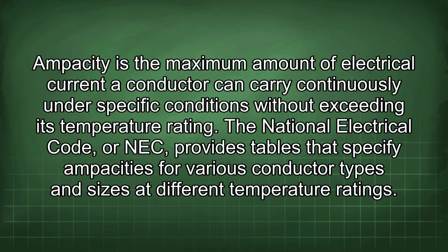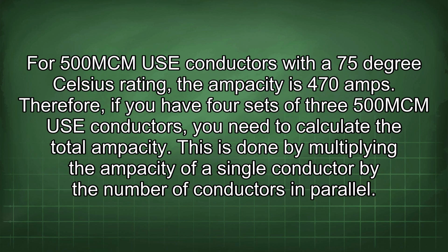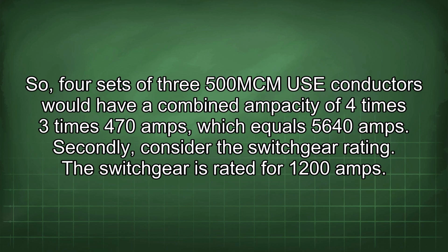The National Electrical Code, or NEC, provides tables that specify ampacities for various conductor types and sizes at different temperature ratings. For 500 mcm conductors with a 75°C rating, the ampacity is 470 amps. Therefore, if you have 4 sets of three 500 mcm conductors, you need to calculate the total ampacity. This is done by multiplying the ampacity of a single conductor by the number of conductors in parallel. So, 4 sets of three 500 mcm conductors would have a combined ampacity of 4 times 3 times 470 amps, which equals 5,640 amps. Secondly, consider the switchgear rating.